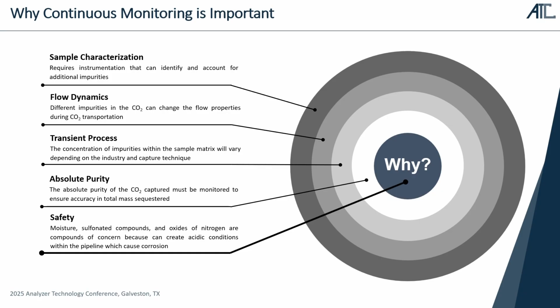The biggest key is safety of company assets. There's basically going to be a custody transfer from the industrial process that's capturing the CO2 to the transportation network. We're monitoring all of these impurities in real time to verify that they do not exceed the limits that'll put the company assets at risk. The next most important reason is for the absolute purity of CO2. This ties to the tax incentives associated with permanently sequestering CO2, whether it's the emission trading system in Europe or a greenhouse gas offset here in the US.